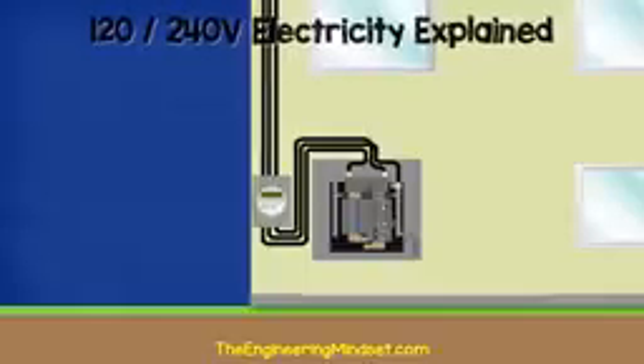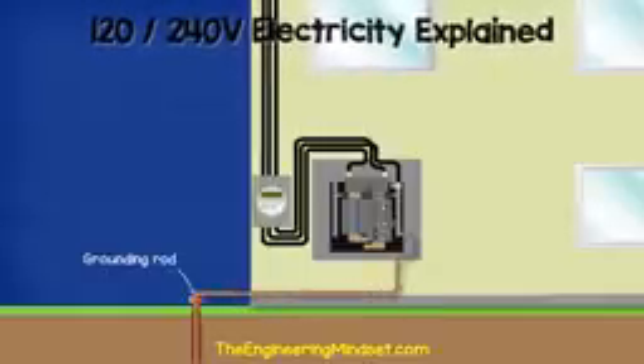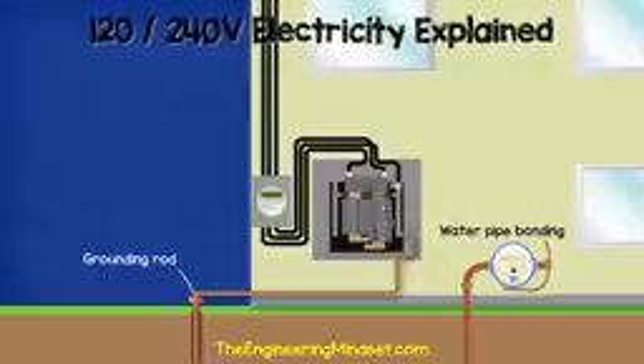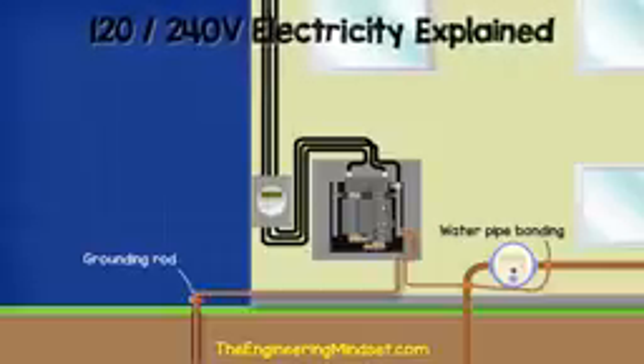Connected to the neutral ground bar will be a thick, uninsulated copper wire which runs out of the bottom of the panel and off to the ground rod, which is pushed into the earth near the property. Under normal circumstances, no electrical current will flow through this wire. Its purpose is to dissipate high static voltages from things like lightning. This way, the electrical systems and equipment are protected from damage. Additionally, we'll also find a bonding wire to metal pipework in the property. This is to provide a safe route for electricity to flow should a hot wire come into contact with a metal pipe, and this way it will prevent a person being electrocuted if they were to touch the pipework.